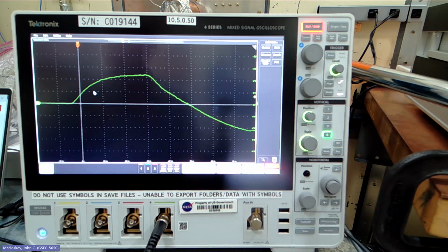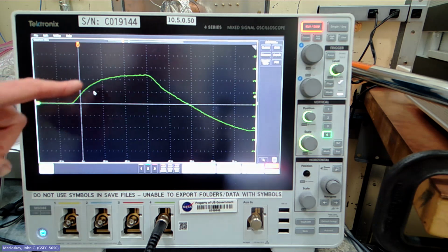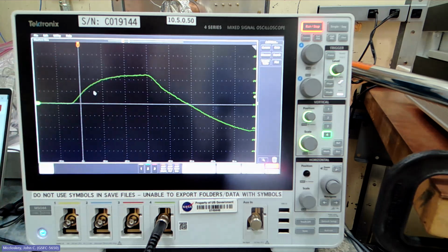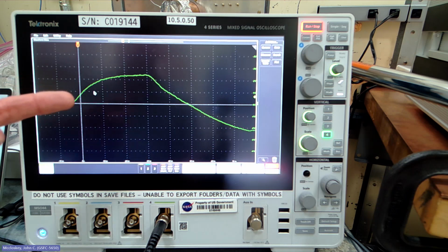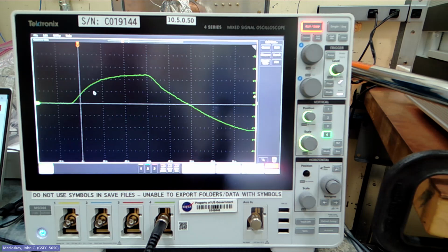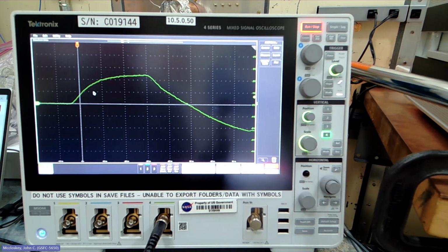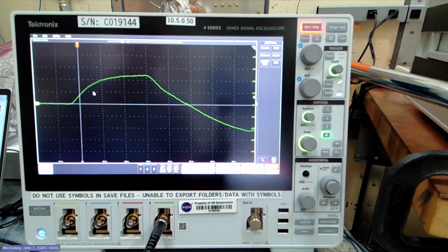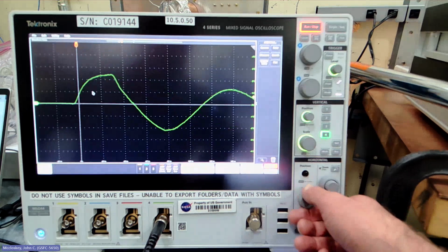And so when I took these measurements before recording this for you, I remembered that factor. I was expecting that it could go up to 15 volts or 15 amps, but when I saw that it was going up to 24 amps, I remembered the reflection portion of it. So it could go up as high as 30 amps, and it's going up to 24, and that makes sense. If it was going higher than 30 amps, I would have to go back to the drawing board and sharpen my pencil and think about the physics of why that's happening. But this makes sense when you consider those factors, and this is the sort of stuff to think about when you're injecting into a real cable under test, that the waveform is going to look pretty substantially different from how it looked into the test fixture.